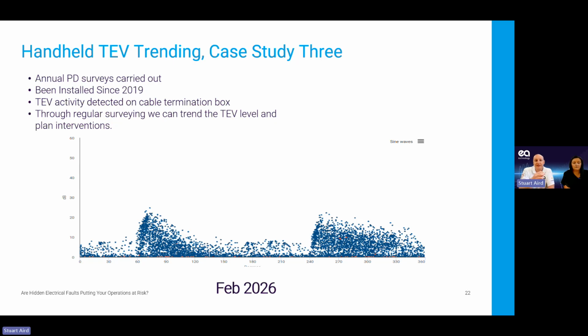You can go there once a year and pick up and trend the activity over time. Whereas in the first two cases, I'd say we were a bit more lucky that you were there at the time and picked it up before the failure. So that's where we're trying to compare the difference with putting a monitor system in. If you put a monitor system in, you know from day one when that partial discharge is starting, and you can plan your actions a lot longer ahead of time. But also, obviously, there's a lot of cost involved in that. So it's getting that balance of whether you need permanent monitoring in the assets or not.